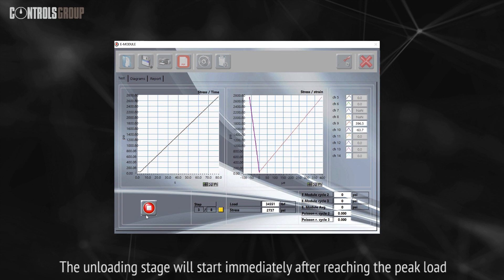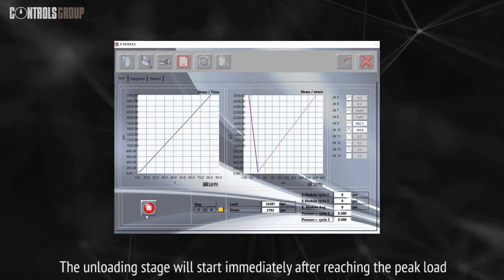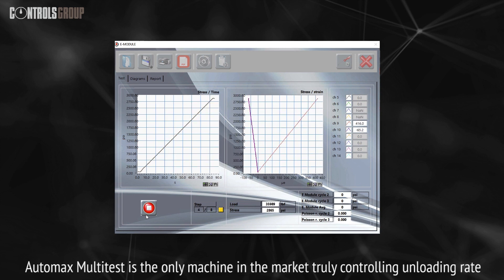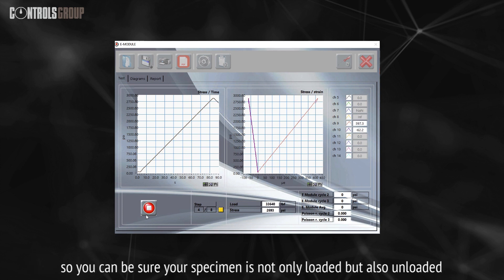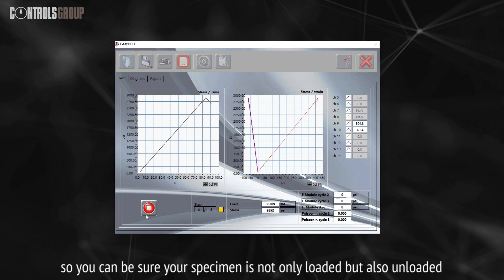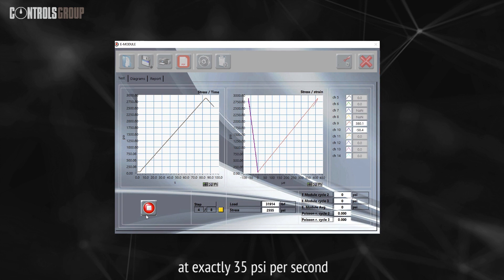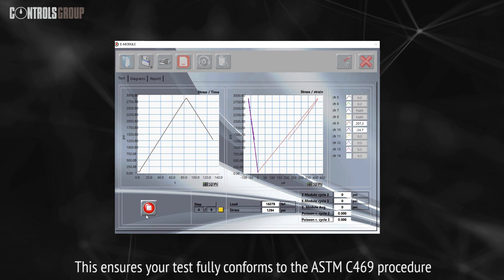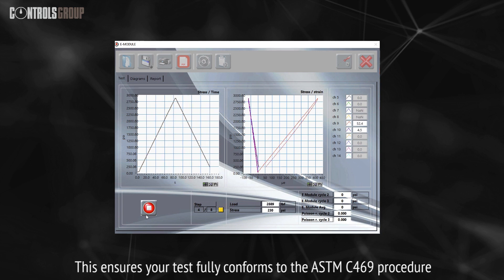The unloading stage will start immediately after reaching the peak load. AutoMax Multitest is the only machine in the market truly controlling unloading rate, so you can be sure your specimen is not only loaded, but also unloaded at exactly 35 psi per second. This ensures your test fully conforms to the ASTM C469 procedure.